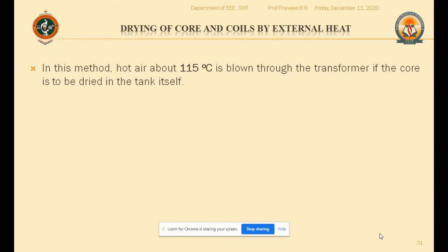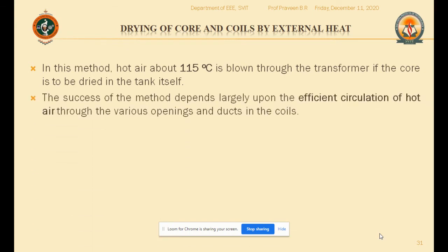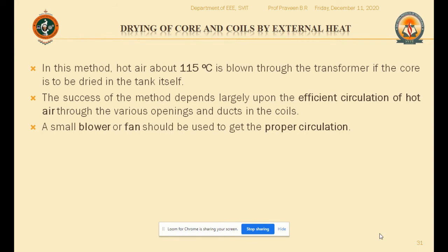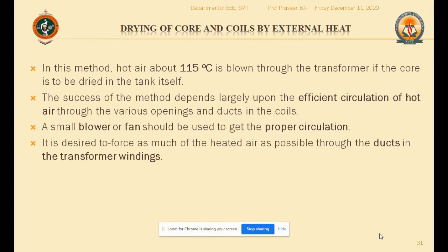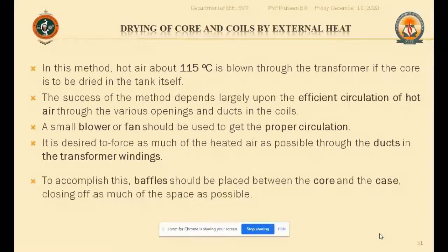So let us see the next, with the oil removed, which is called external heat. You pass hot air at 115 degrees centigrade, blown into the transformer tank such that the cores are dried in the tank itself. The hot air is circulated efficiently in such a way that the ducts and the openings are dried up. You may also use a blower or a fan for proper circulation. And these ducts will also need to be dried for the transformer windings.